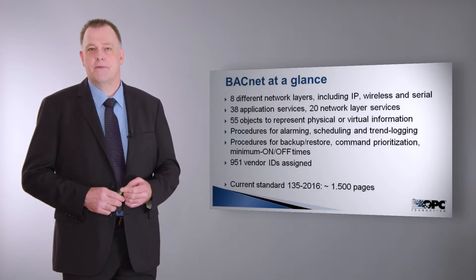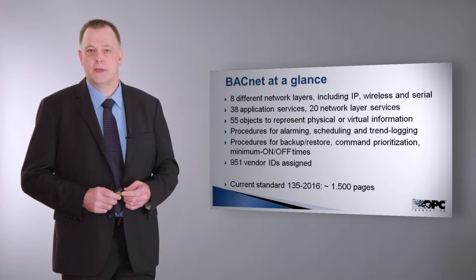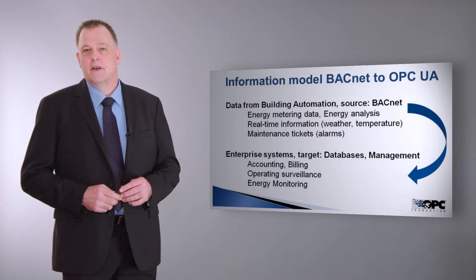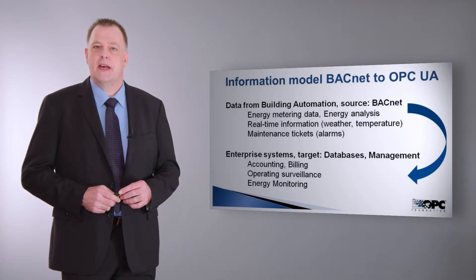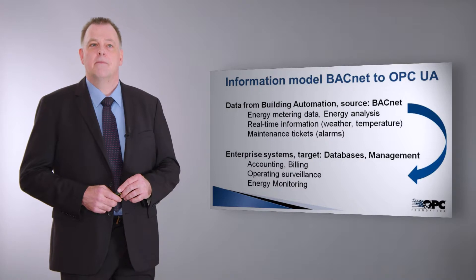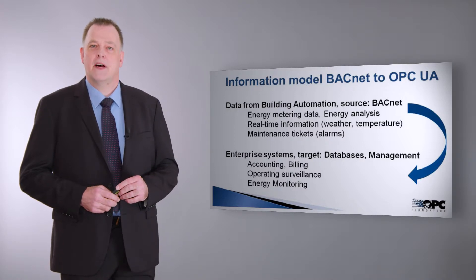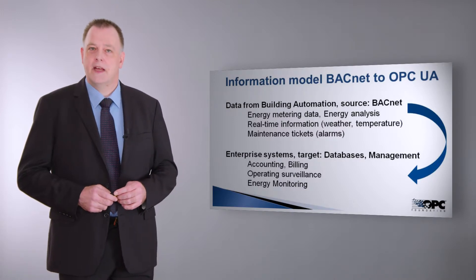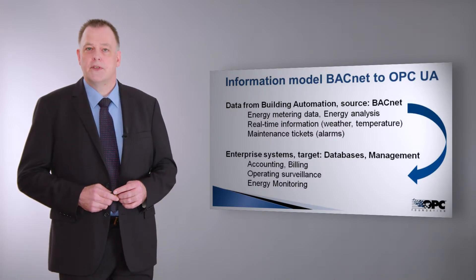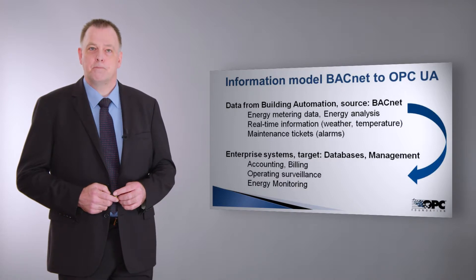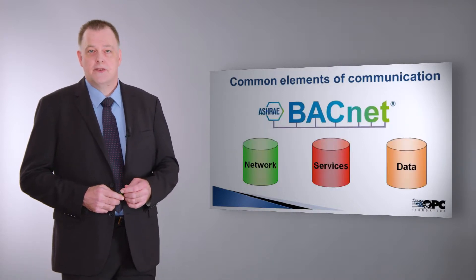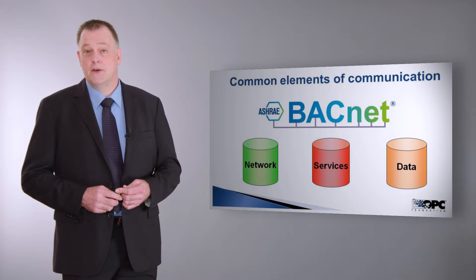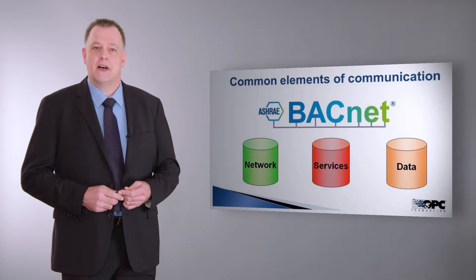More than 950 vendors have already subscribed for getting a vendor ID and are known as BACnet manufacturers worldwide. The current standard has more than 1500 pages in total. The information model for connecting BACnet to OPC UA is simply a data model where we specified how to present the BACnet objects and their properties and map this into enterprise systems using the OPC UA structures. In every communication protocol you need to specify the network media, the services, how to transport the data, and the data itself.